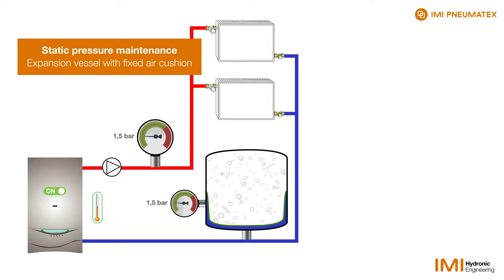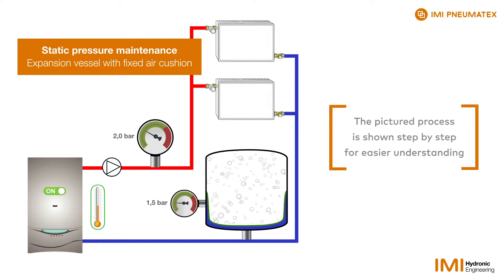When the boiler is switched on and the water heats up and expands, the pressure increases, for example to 2 bar. Water is forced into the vessel and compresses the gas on the other side of the membrane to 2 bar.